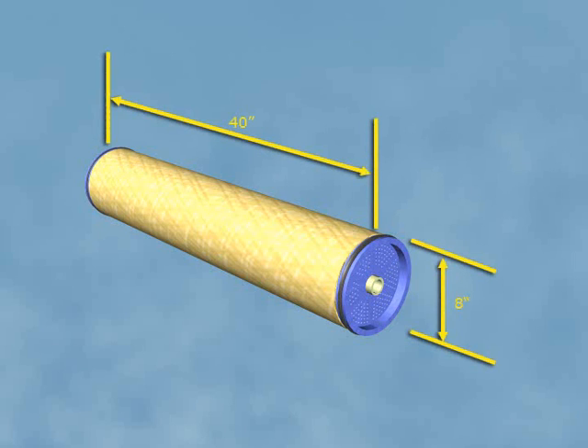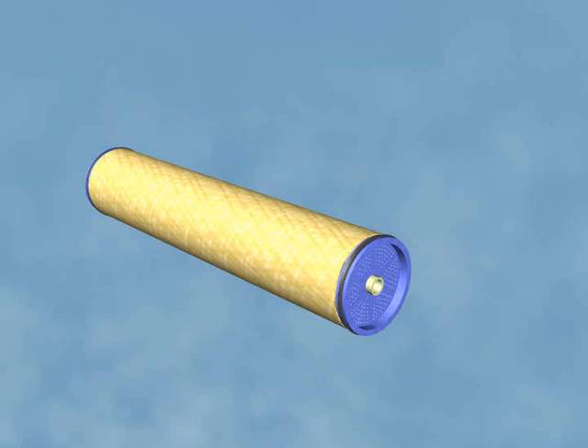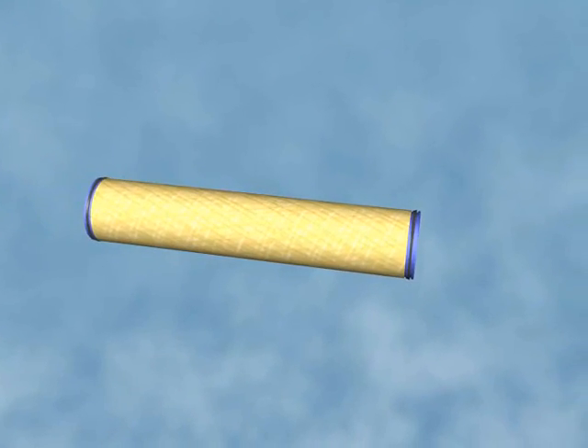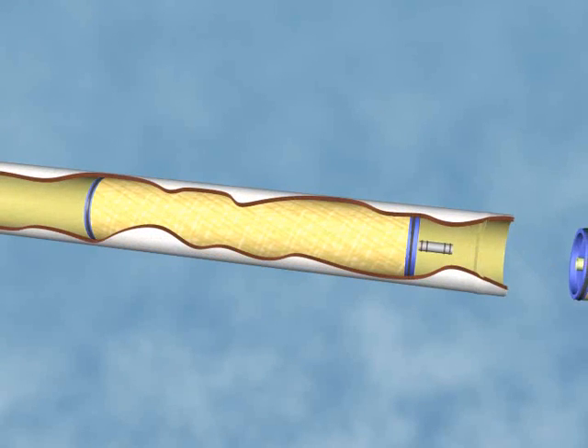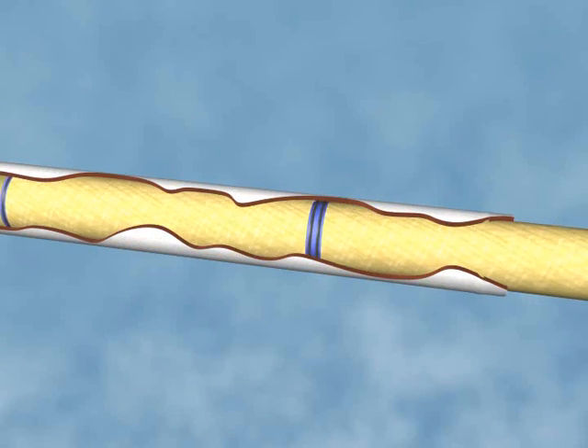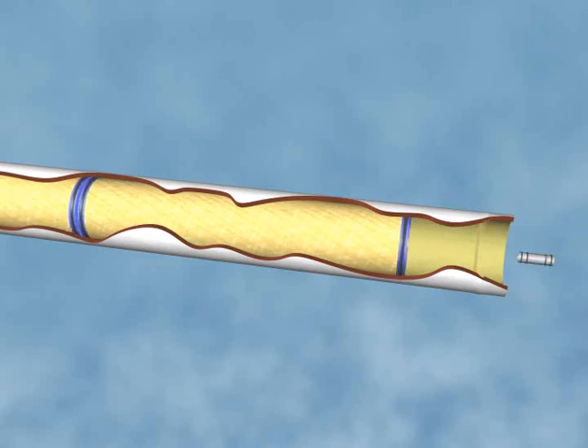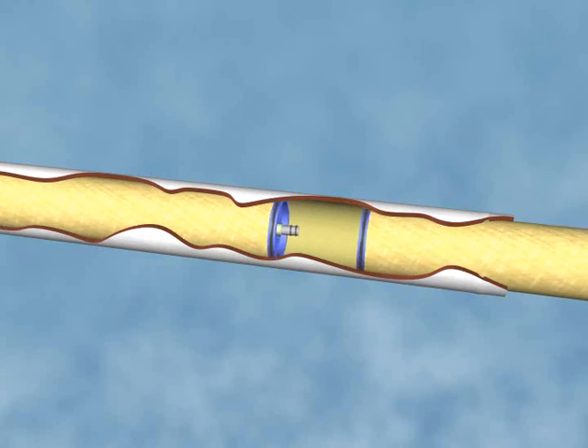A very common size used for industrial water purification is an element which is 8 inches in diameter by 40 inches in length. When six elements are placed in a pressure vessel, male couplers connect the product tube in each element to the product tube of the next element. This interconnection allows permeate from all elements to exit the pressure vessel in either direction.